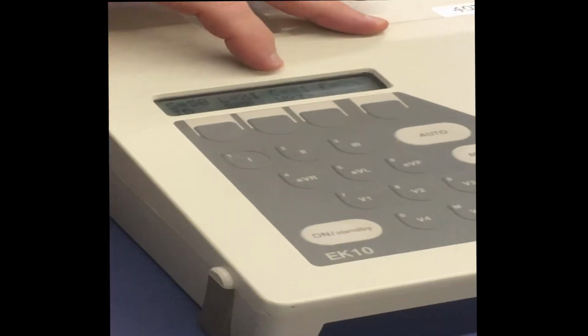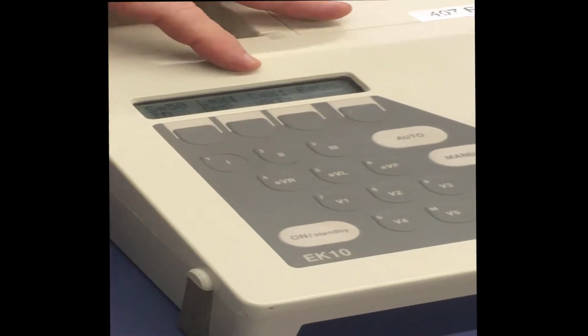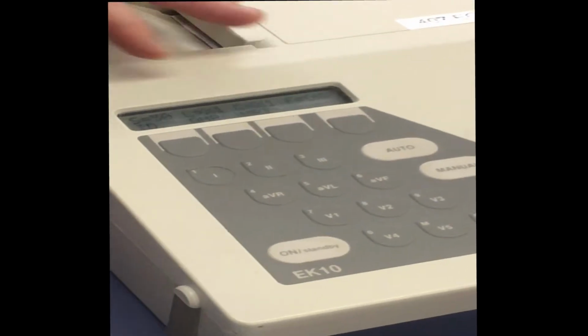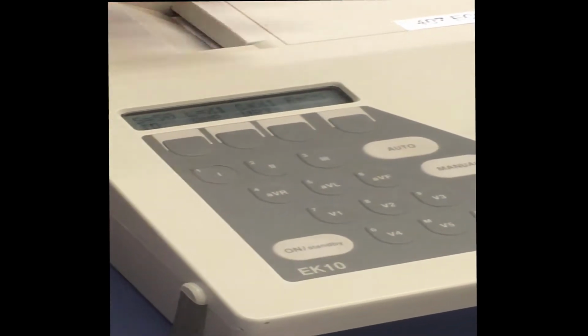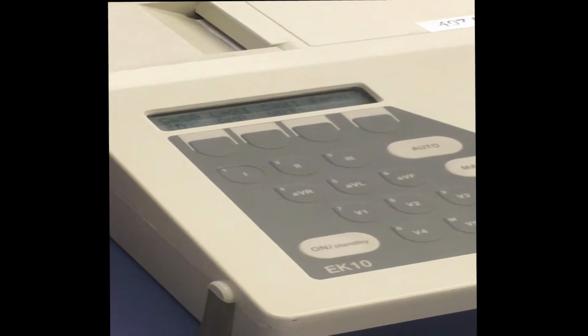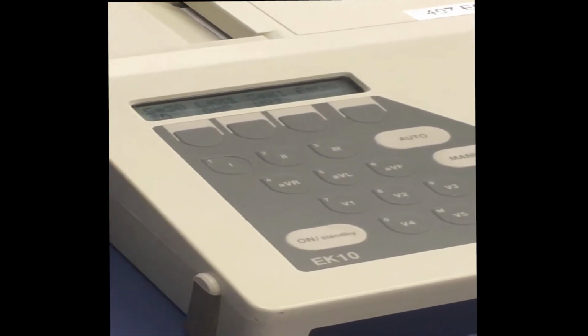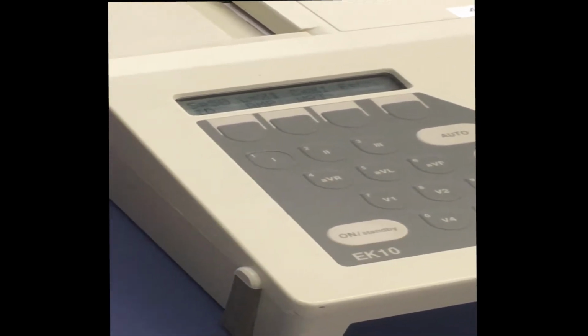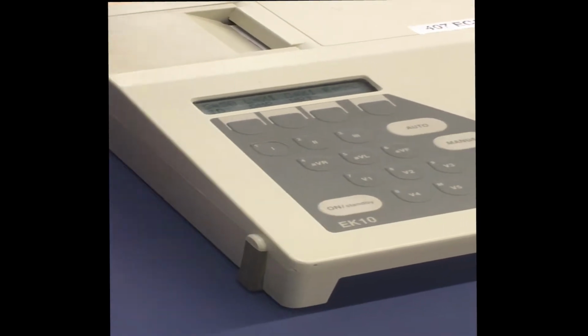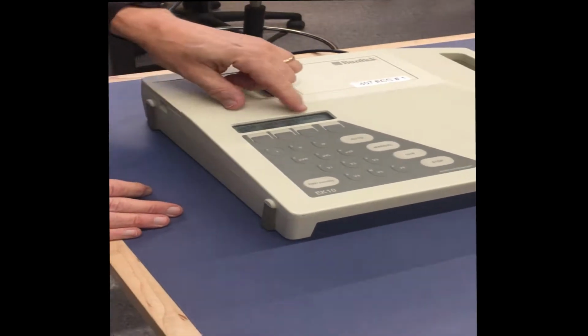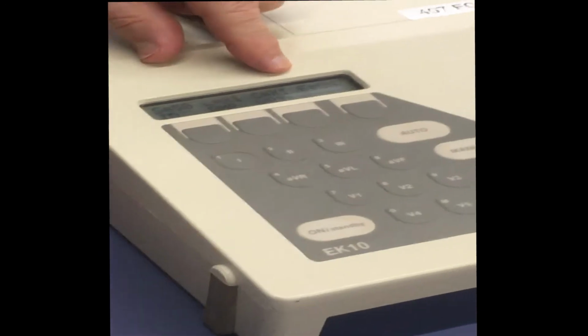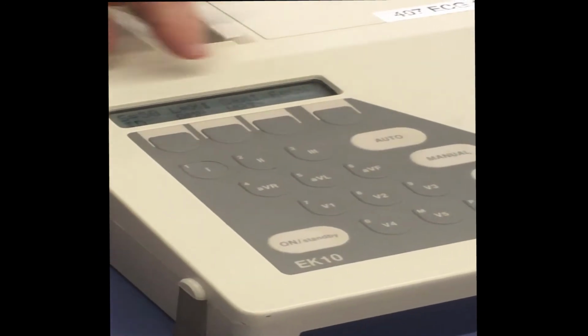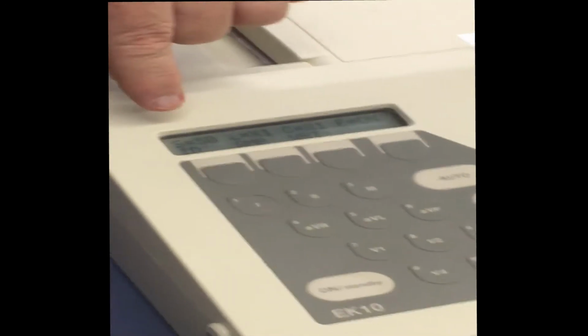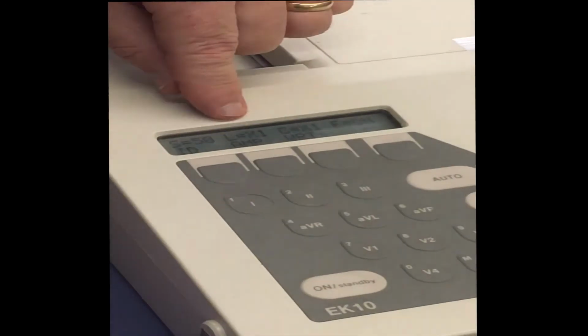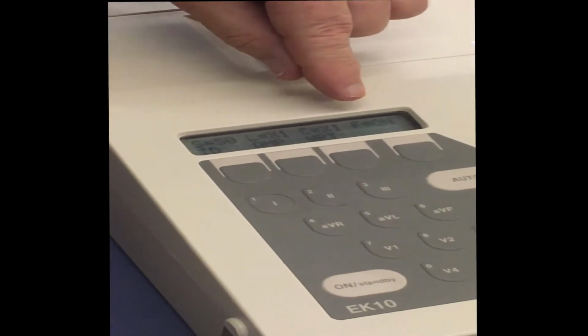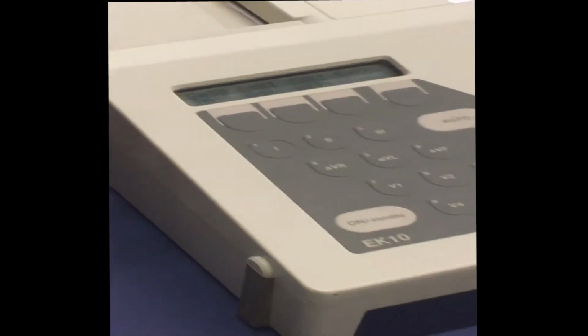The next gain is the C for the chest. So there's a separate gain for the limbs and for the chest. Right now the chest gain is on 1. The only thing you can do with the chest gain is half it, because typically the electrodes are close to the heart, so you're going to get a very good signal. But if your signal is too large and it's going off the trace, then you can half it. And the last thing on top is for the filter. So right now it says filter is on. So right now I'm looking at the 4 numbers. It's saying the speed is at 50, the limb gain is at 1, the chest gain is at 1, and the filter is on. So those are my 4 settings.